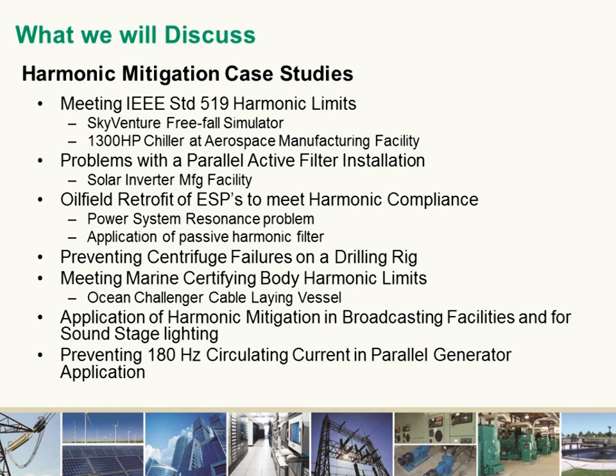levels exist. We'll learn how one ship, a cable-laying vessel, saved valuable deck space and significant cost after eliminating the need for rental generators by filtering harmonics to meet marine certifying body harmonic limits. We'll explain how passive electromagnetic devices can be used to eliminate harmonics in broadcasting facilities and film studios. And finally, show how we resolved very high neutral circulating current that was created when generators of dissimilar pitches were paralleled.